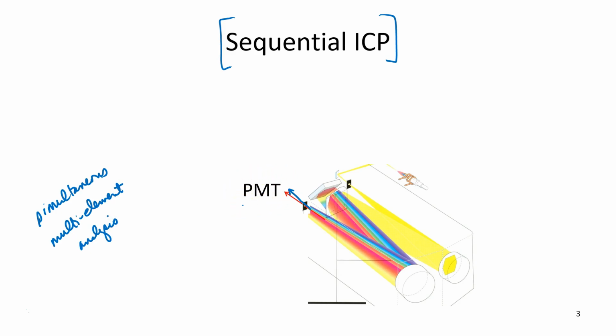It'll just take a little bit longer because you have to make your measurement, rotate the grating, make your measurement, rotate the grating. It's still better than using a separate hollow cathode lamp for each element and only being able to analyze one element at a time, which is how you would do it in Flame AA.